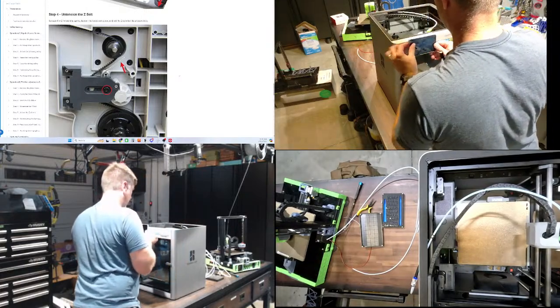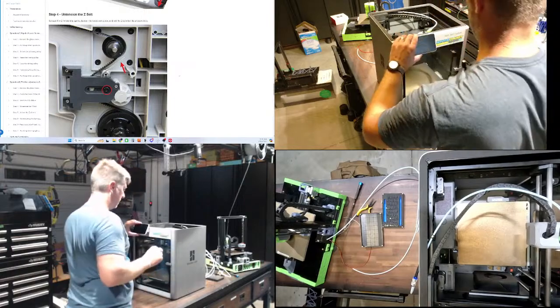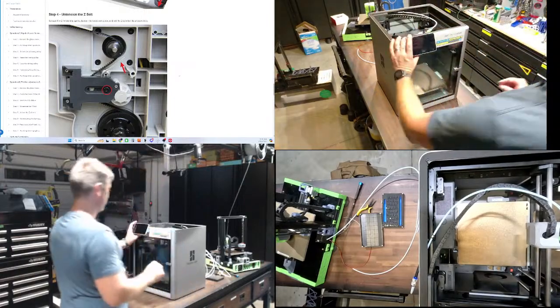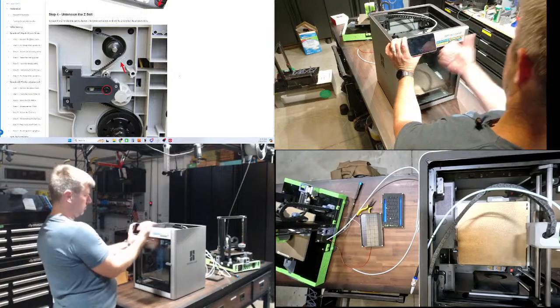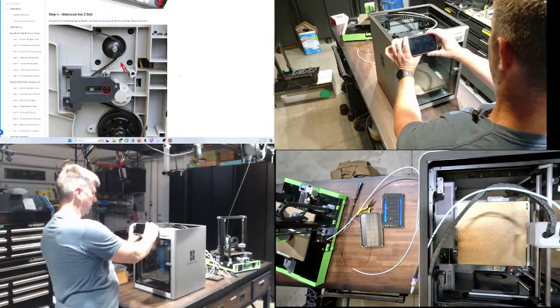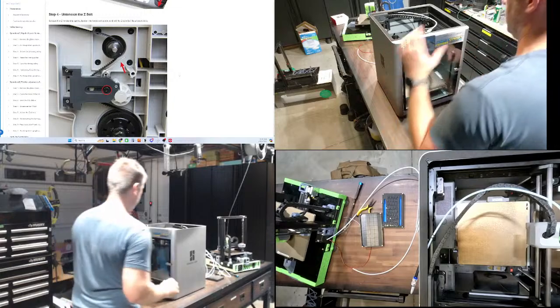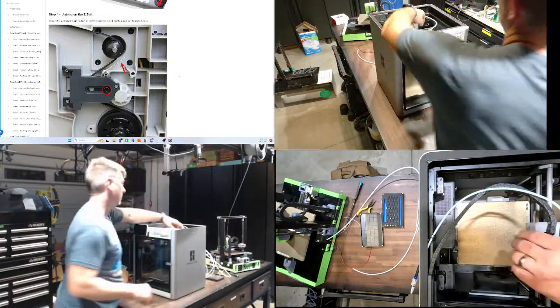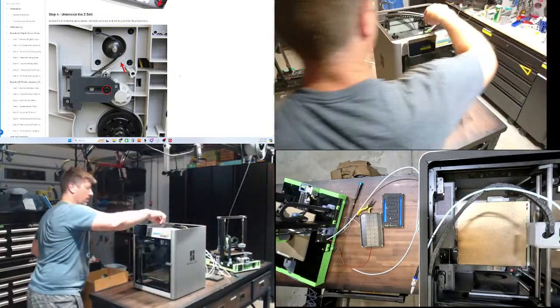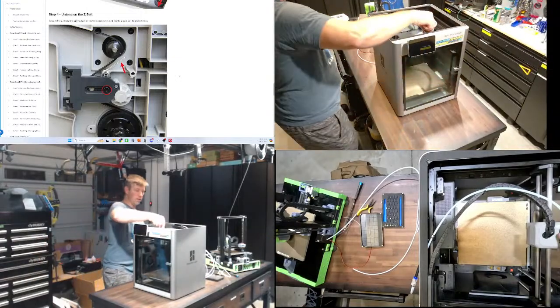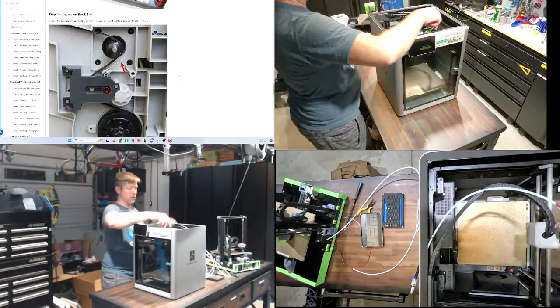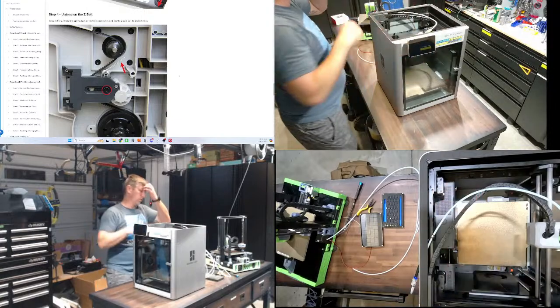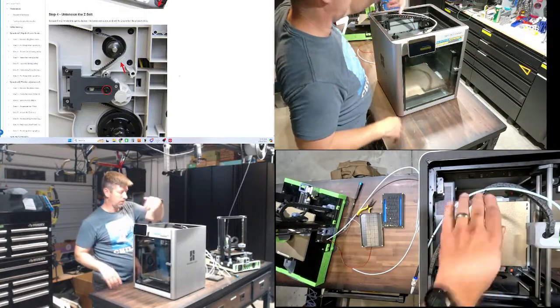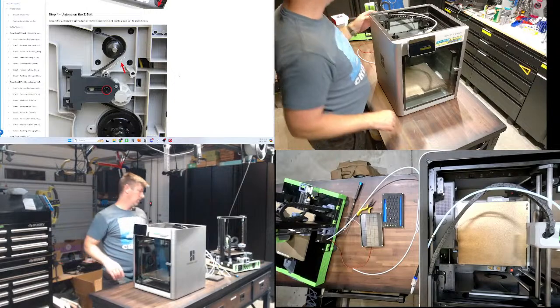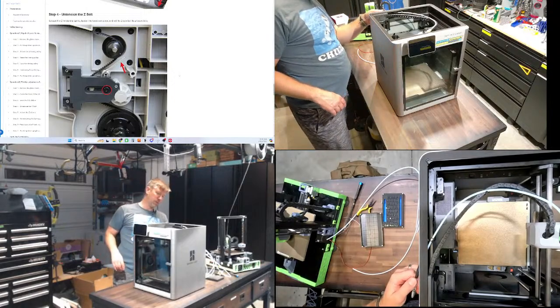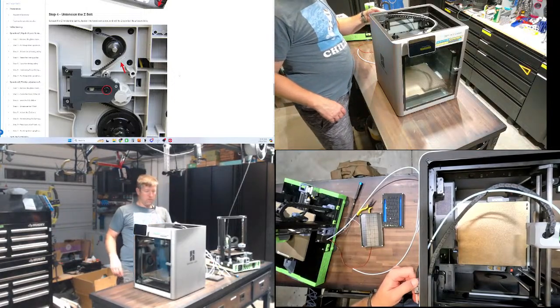Alright, once the screen's connected, we're going to pop that back into its spot. To release the screen, there's a little dimple on the bottom: you press up and rotate it, or push it to the right, and it'll unlock, and lock it back down. You'll have to take the screen off when you flip the unit upside down so you can access everything. You can see here I also have these handy guides on top of the PTFE, which help keep it from rubbing across the glass and putting shards of Teflon all through the unit, because I don't like having Teflon inside of it. But you know, neither here nor there.